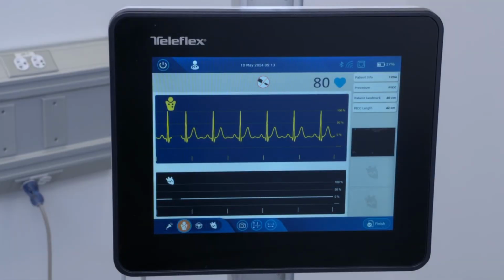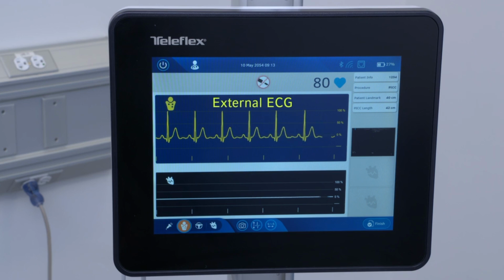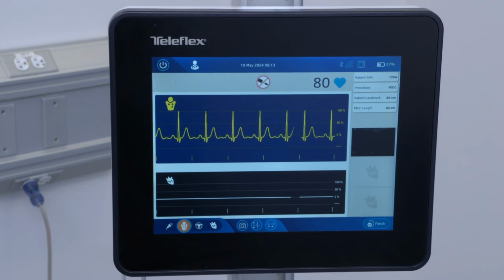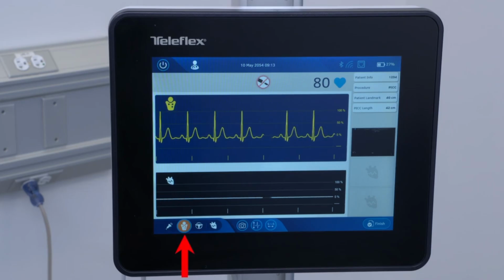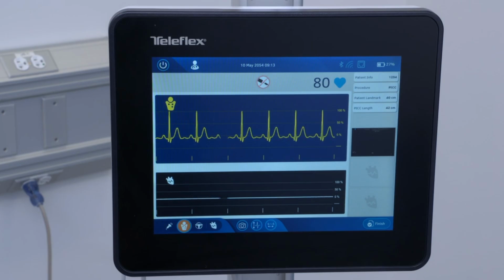Verify the monitor is in external ECG mode. Please note that the external ECG waveform is yellow on a blue background and has the yellow icon. The external ECG icon can also be seen in orange at the bottom left corner of the device, confirming you are in external ECG mode.